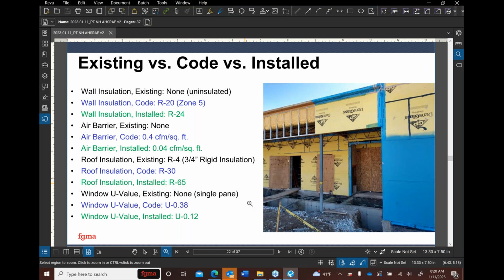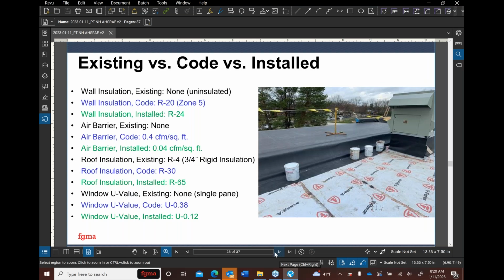Roof insulation, the existing was put on in the 1980s, about an R4, with 3/4 inch of rigid and tar and gravel on top. Our code requirement would have been R30, and here's probably the most dramatic increase: we did an R65, so the tapered insulation was 10 inches thick at the roof drain and tapered up to over 2 feet thick at the roof edge. This is an installation photo while the roofing was going on—those are 5-gallon buckets sitting next to a completed area of roof, and you can see the insulation thickness is taller than a 5-gallon bucket.